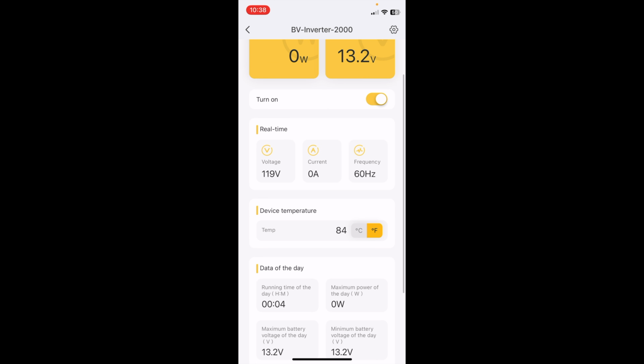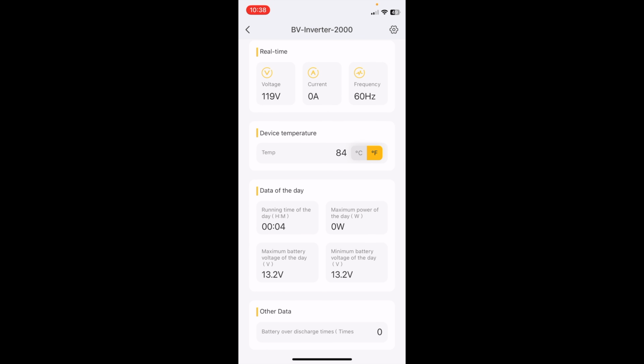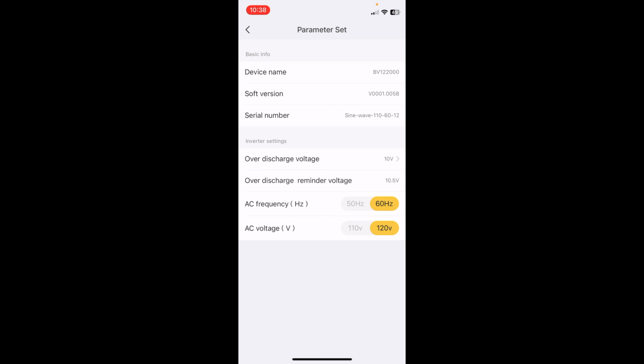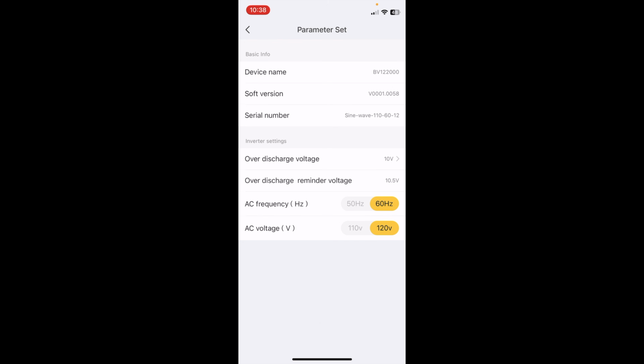There's interesting things you could do in here, mainly because you can go into the settings and set the over discharge voltage settings. If you had lead acid batteries that could get damaged from discharging too low, that matters. Lithium iron phosphate or LiFePO4 batteries usually have a BMS built in that prevents over discharge, so I usually don't have to worry about that. But in case you do, that's where you'd set it.